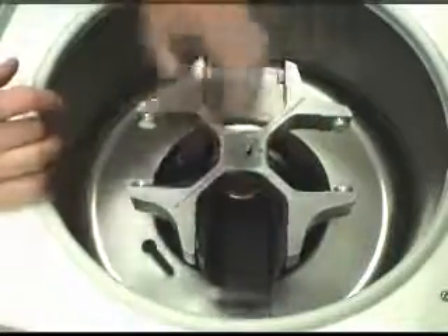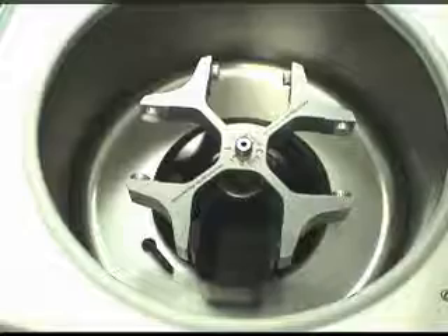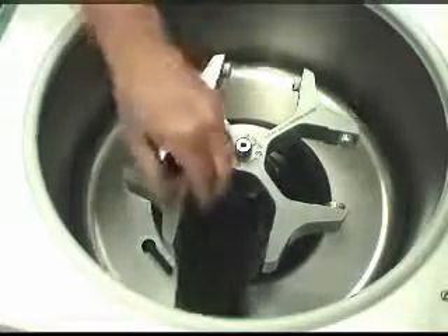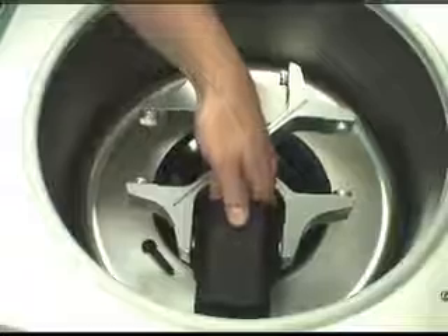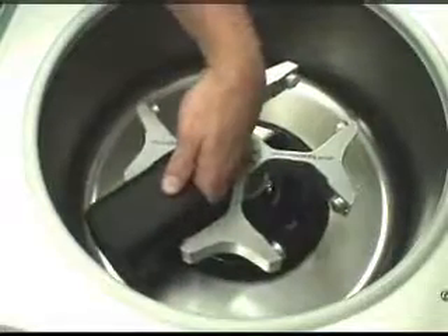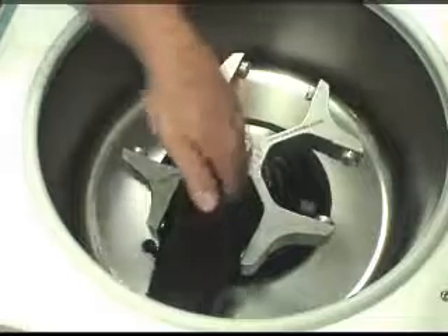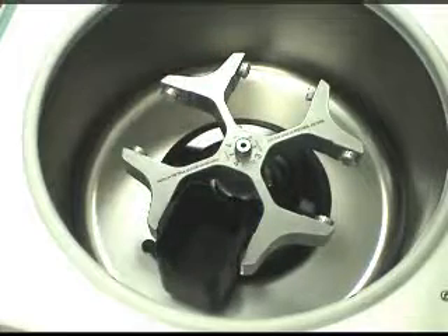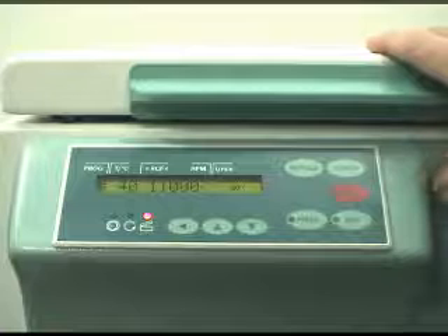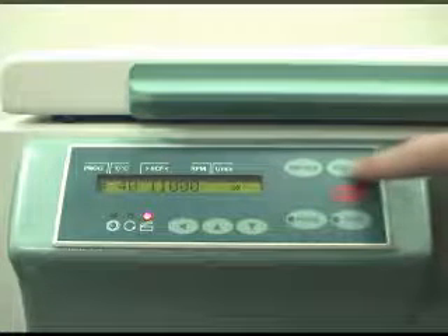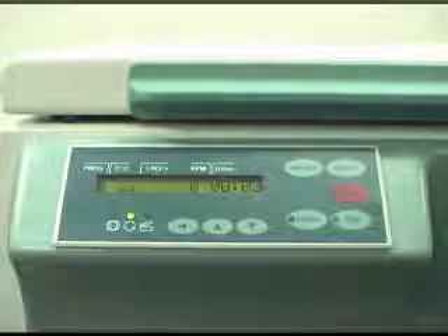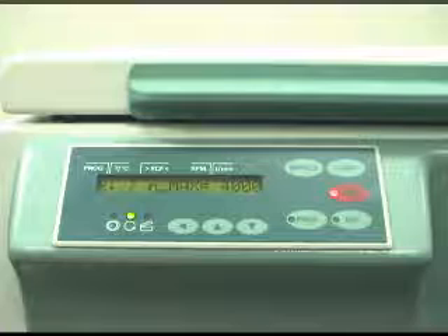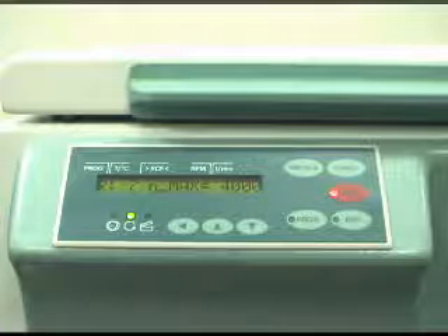To know that you've done a good job, you should be able to pendulum that bucket by pushing it off center a little bit, and it will swing back to position. The idea of the bucket is to be able to swing out fully to 90 degrees in all 4 positions simultaneously, so as not to induce a vibration or an imbalance. Once all 4 buckets are lubricated and hung in there, close the lid, press the start button. The centrifuge should spin up, recognize that there is a new rotor in place, and spin down automatically.